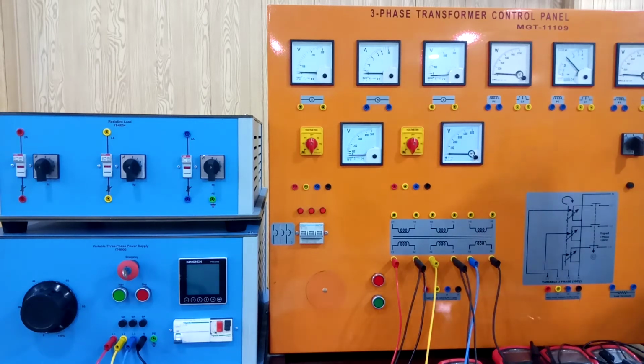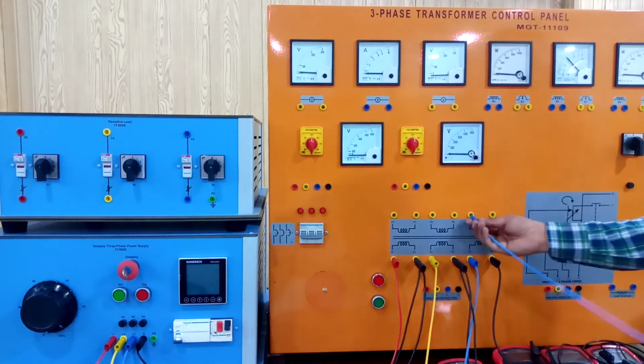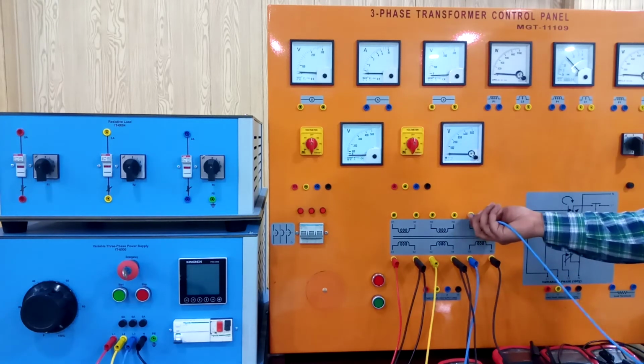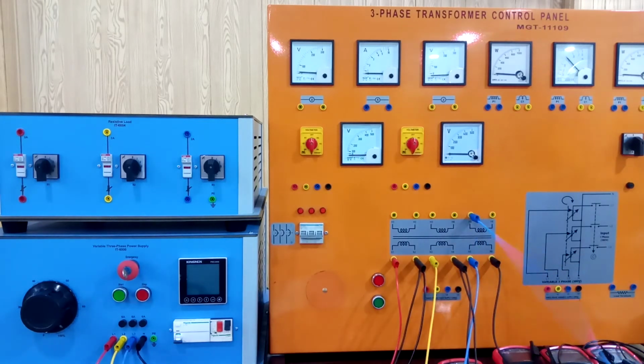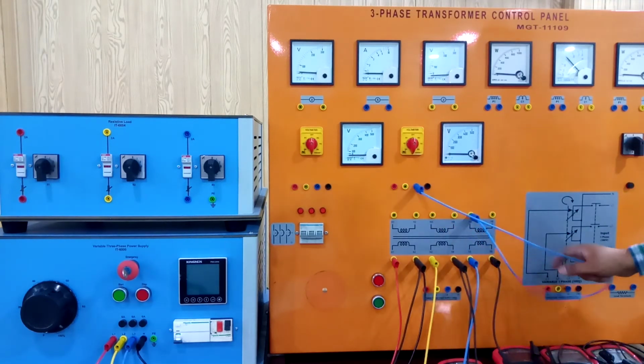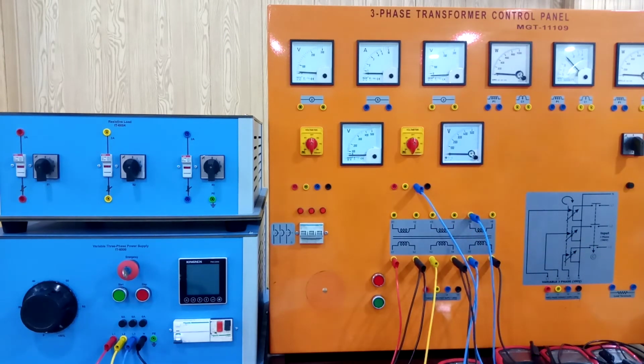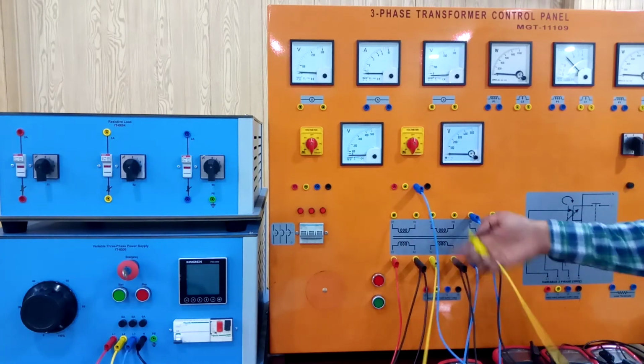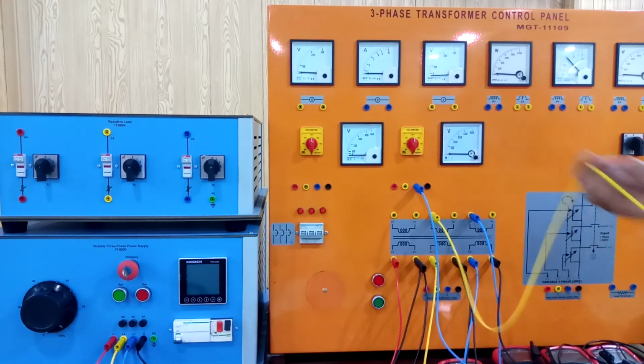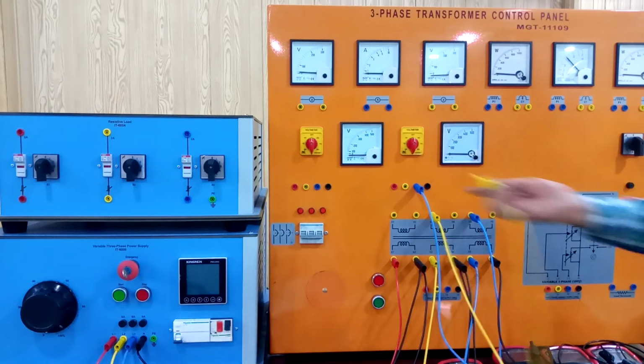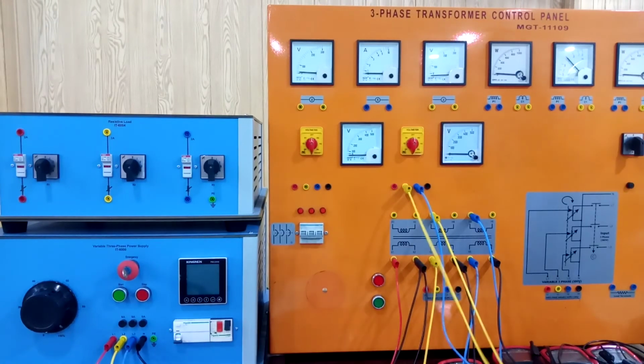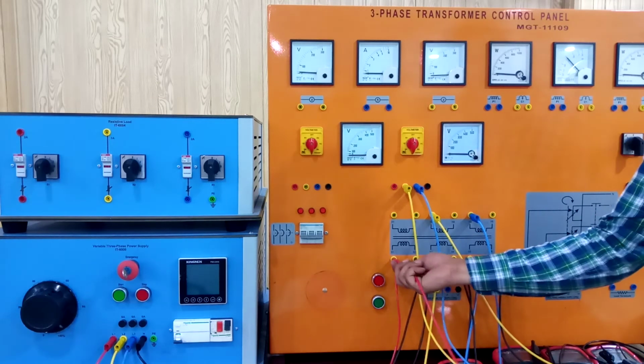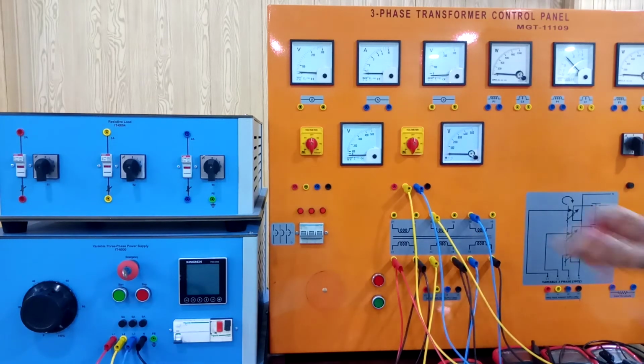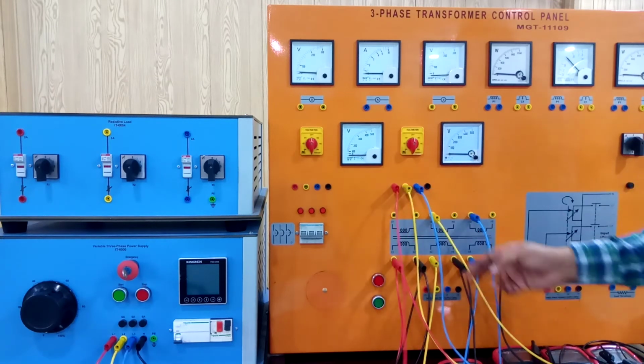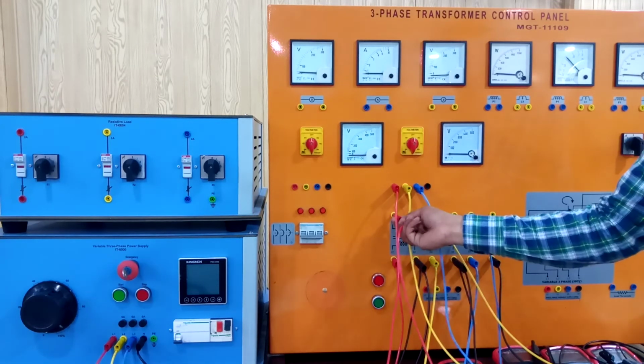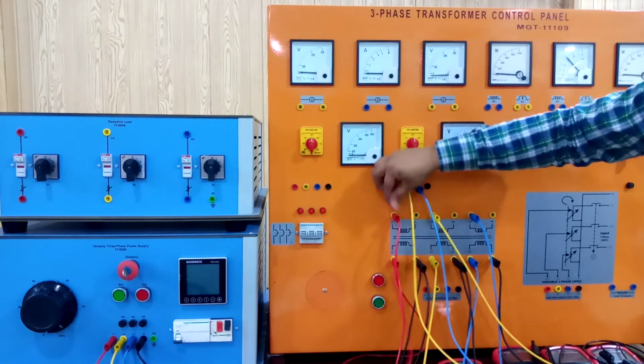So it's very simple. Just connect the three phases: the blue phase here should be connected with the blue terminal of the selector switch. So this is our first connection. Then the yellow connection of the secondary, or the low voltage side, is connected here, and then the red phase has to be connected with the selector switch. Okay, sorry, this one. So this is the connection here.